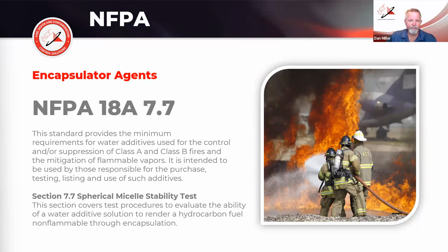After we go through an encapsulator stability test, we put a torch on the surface of the liquid that we ran the test on, and it does not reignite, even in the presence of direct flame contact from a torch. So it not only cools and encapsulates, it locks up those carbons and hydrocarbons and keeps them from being available to combustion for a long time.